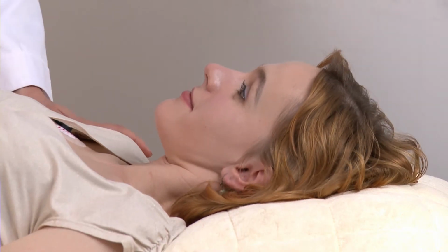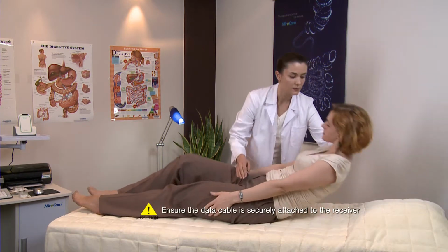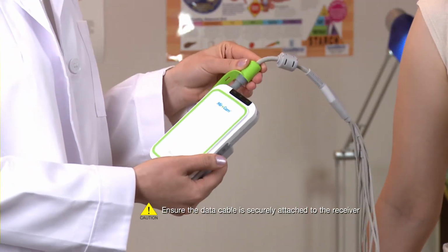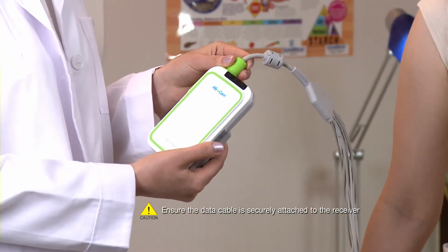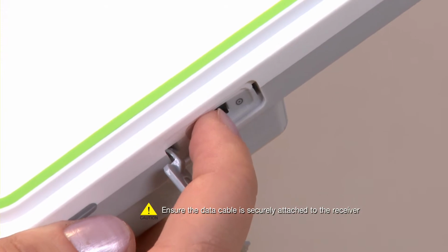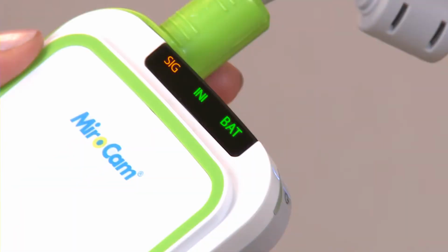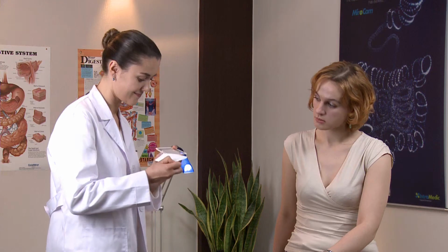After attaching the sensor pads, have the patient sit up and connect the data cable to the receiver. Turn on the receiver and check the battery indicator. The SIG icon should be orange, and the INI and BAT icon should be green. If the INI icon is orange, the receiver needs to be initialized. If the BAT icon is orange, the battery needs to be charged.